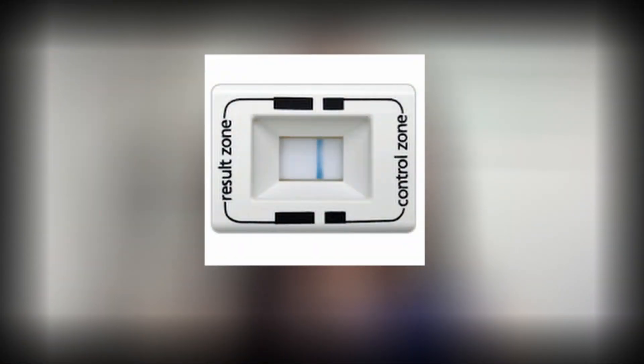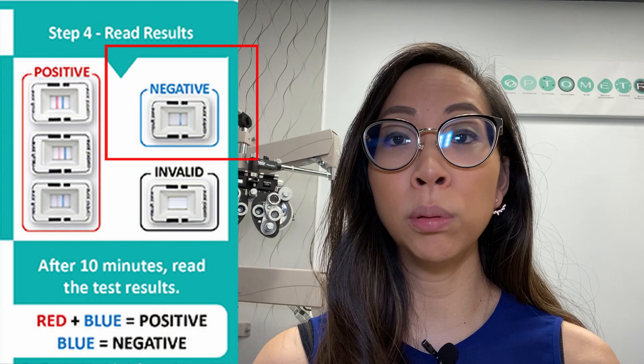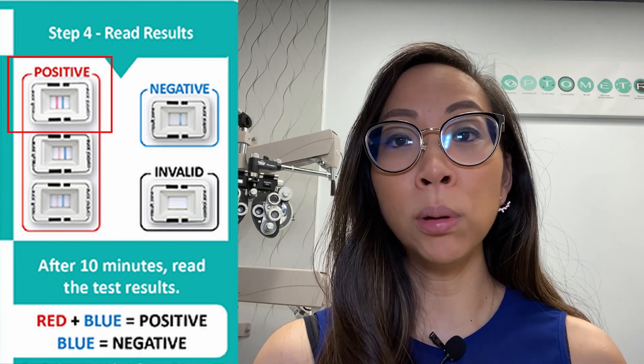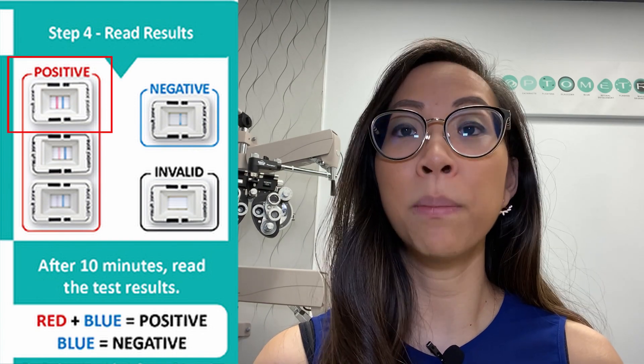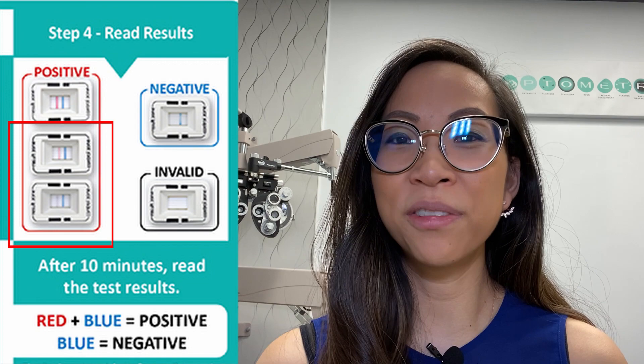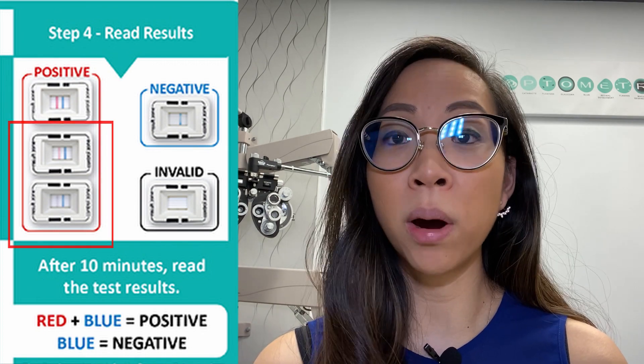The results are read in a similar way to at-home pregnancy tests — it essentially gives you a yes or no answer. If the test is done correctly, there will always be a blue control line. A solitary blue line indicates a negative result, but signifies an accurate and valid test. A blue line along with a solid red line is a positive test. A blue line along with an uneven, incomplete, or even a faint red line is also a positive test. A positive test indicates the presence of MMP9 greater than 40 nanograms per milliliter in the tear sample, and anything below that registers as negative.